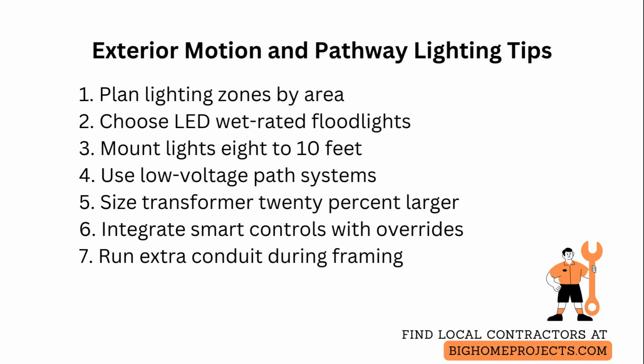Mount them between 8 and 10 feet high and angle them down and away from windows to prevent glare into neighboring homes. For pathway lighting, use low-voltage 2-wire systems with a transformer sized at 20% above the total load and set timers for occupancy patterns, or pair them with a photoelectric dusk-to-dawn cell to avoid daytime runtime.